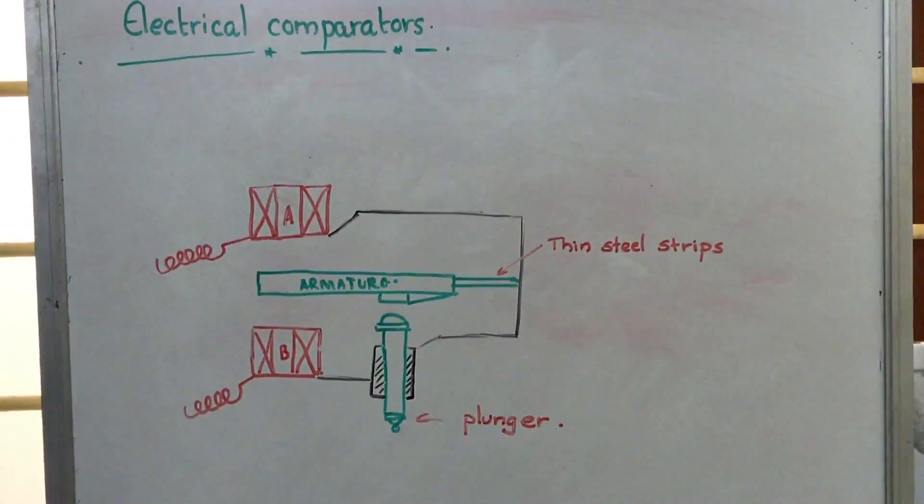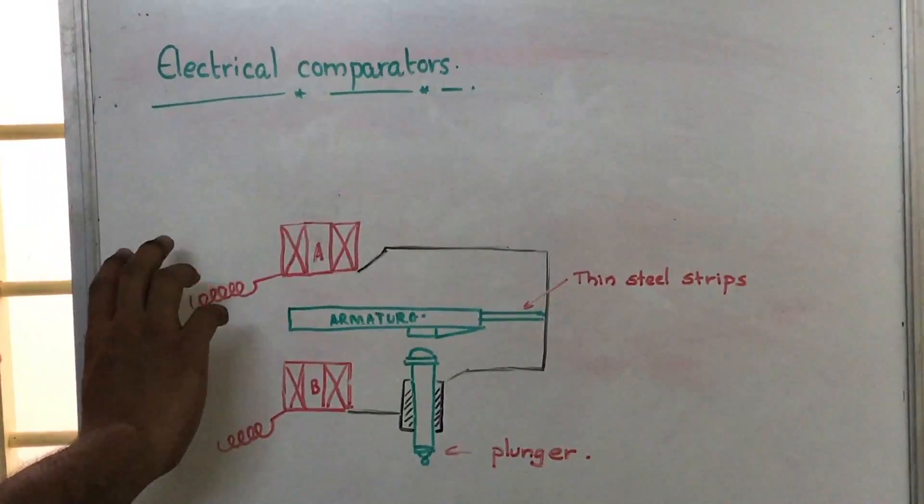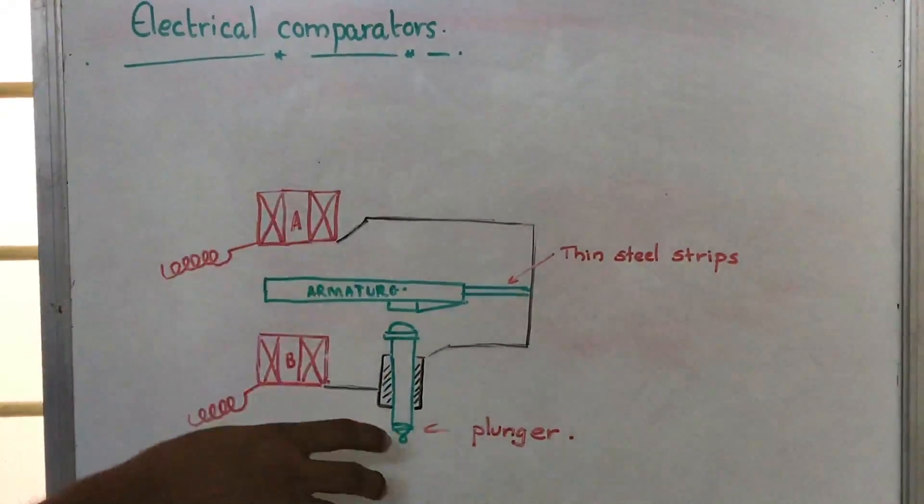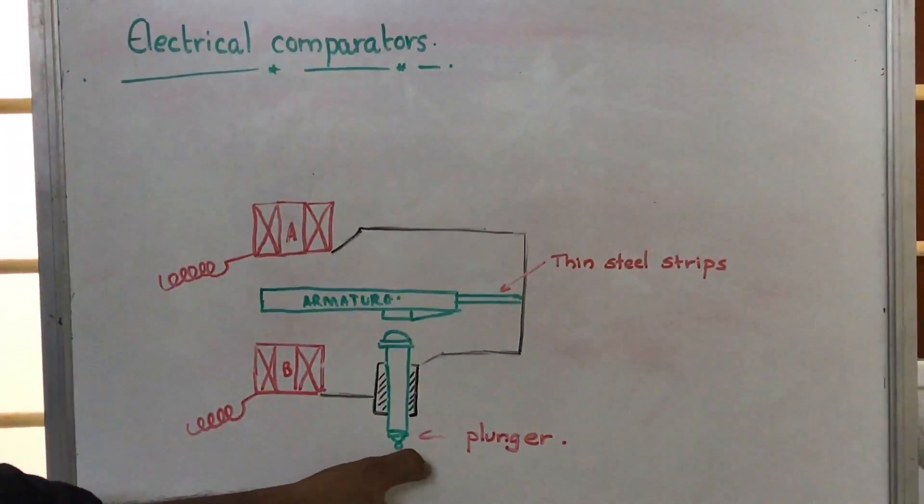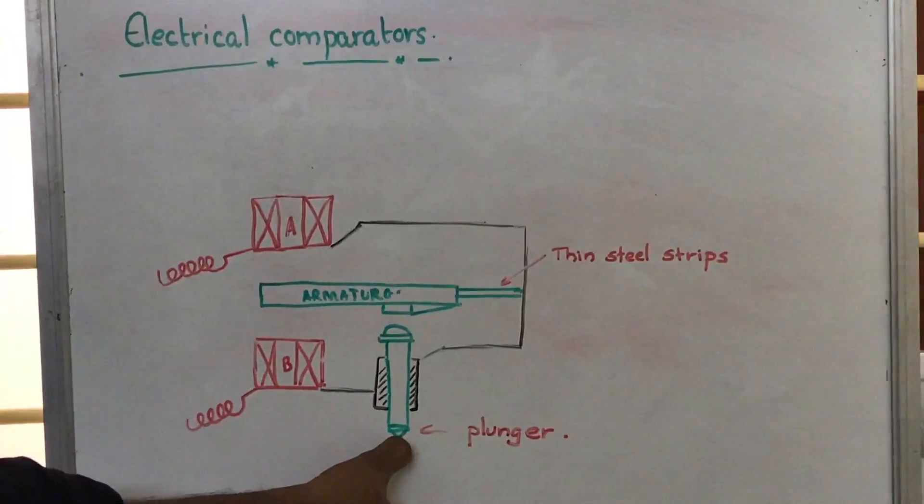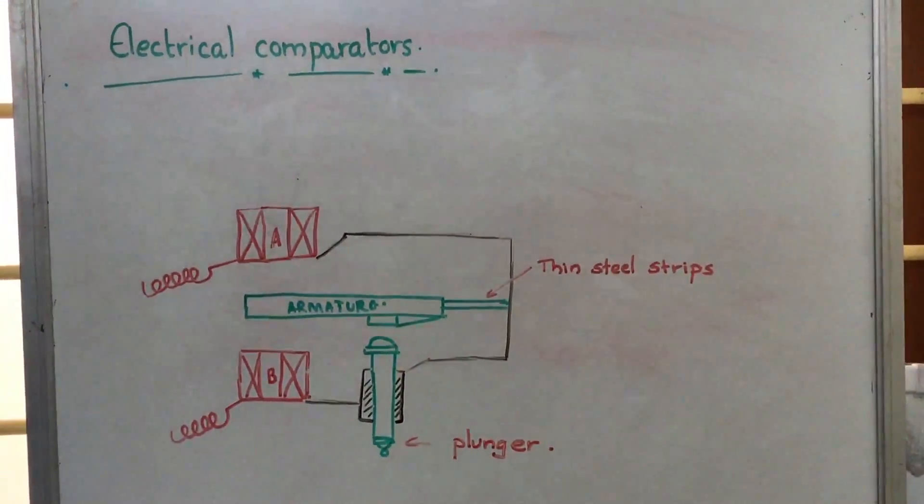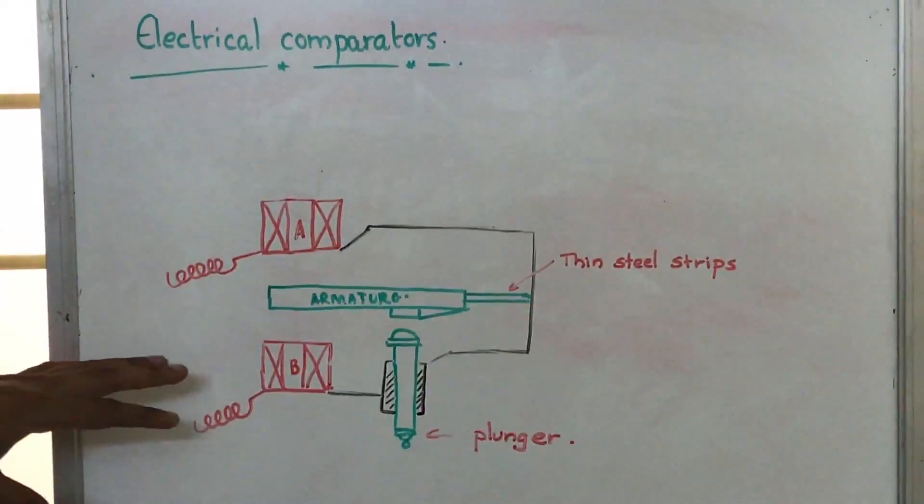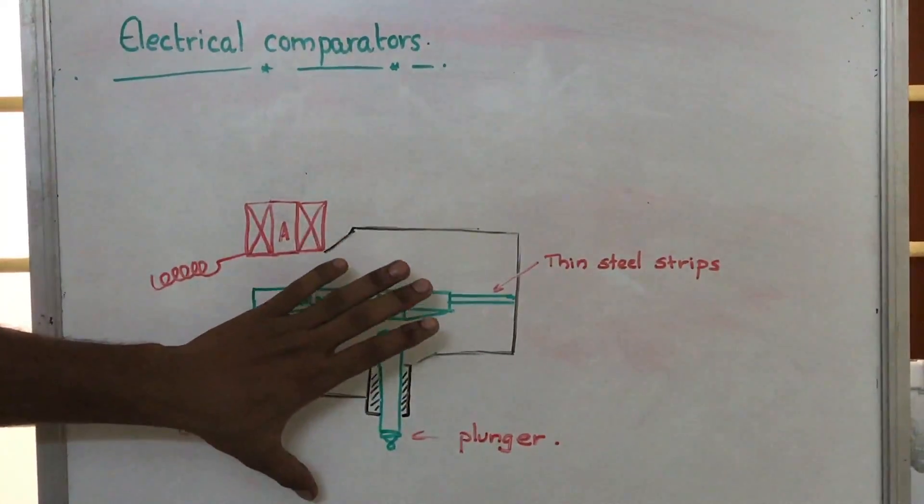The galvanometer will show a deflection, and that deflection will be calibrated to the movement of this plunger so that we can obtain the movement of the plunger or the dimension of the object inserted beneath it. We use a Wheatstone bridge and a plunger-armature system to measure it.